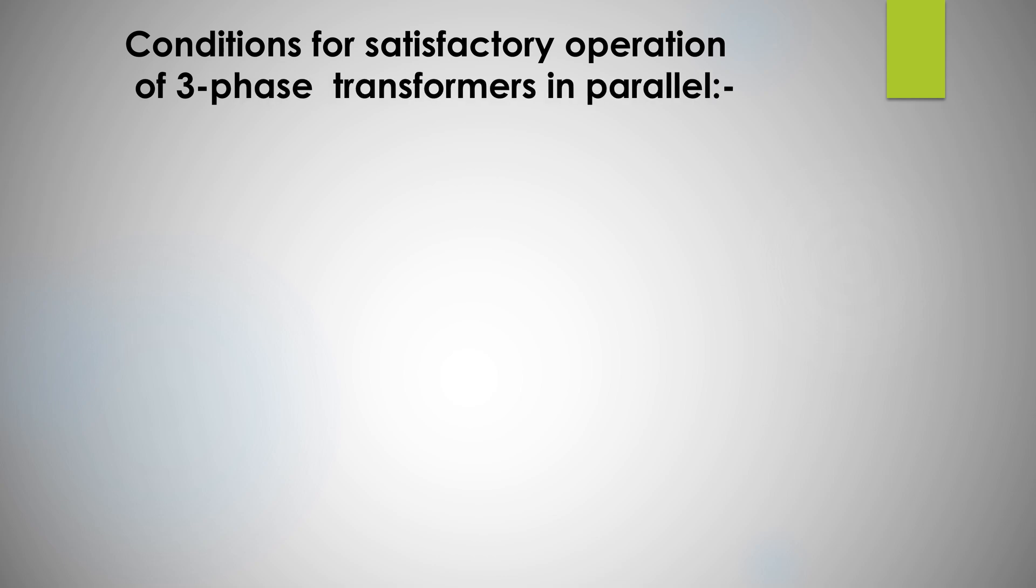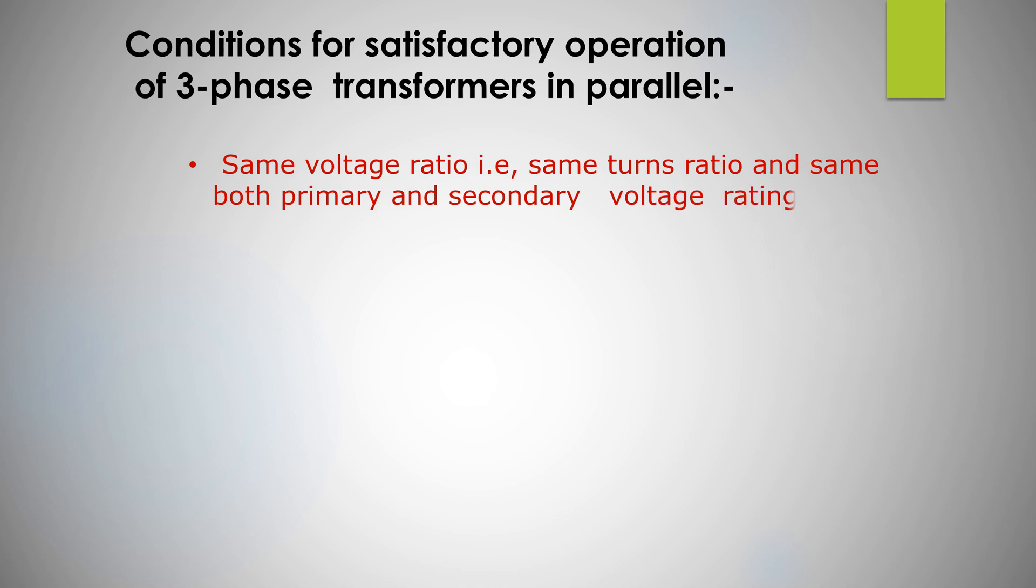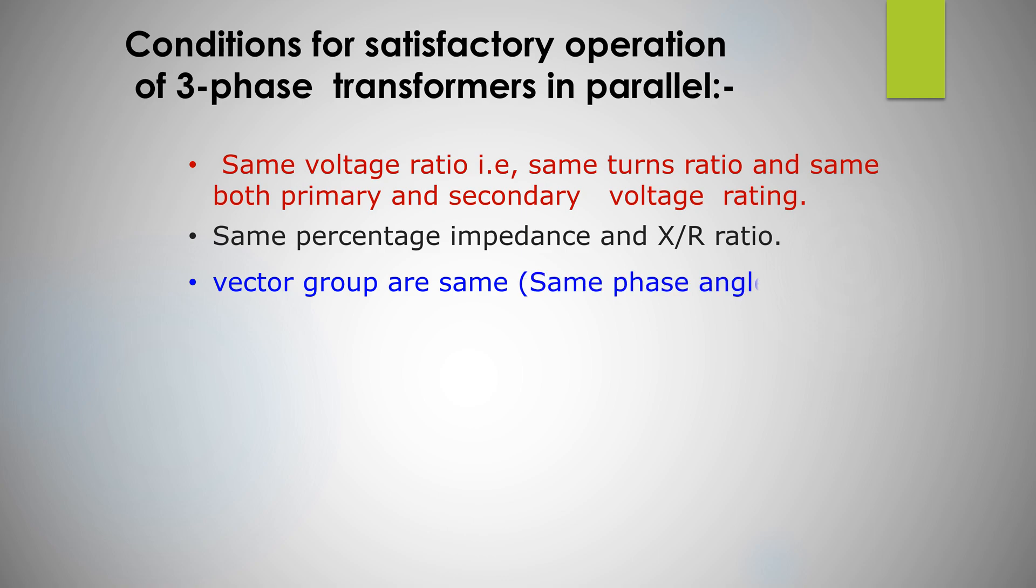Conditions for satisfactory operation of three-phase transformers in parallel: same voltage ratio, that is same turns ratio and same both primary and secondary voltage rating; same percentage impedance and X/R ratio; vector group are same; same phase angle shift.